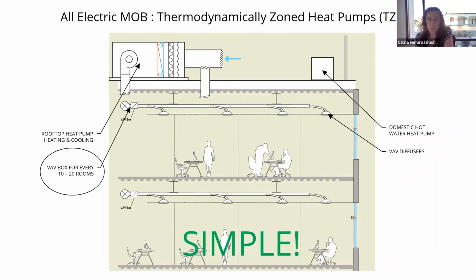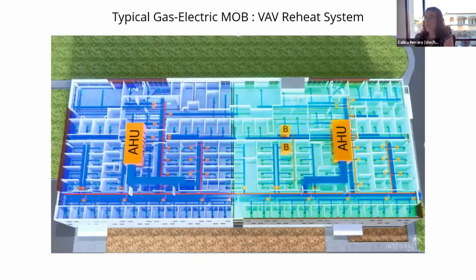You'll also notice there's a lot less mechanical stuff on the page. It ends up reducing the amount of equipment, materials, and also labor for installation, by being able to do all of that at the roof instead of needing to run those additional systems. To give you more of a picture of what this looks like, this is what that conventional system would look like. You can see central air handling units, large ductwork from central distribution taking up that ceiling space, running those large duct mains to get to that full zone, and then this separate hydronic boiler system. And you can see the heating hot water piping routed from that to each of these zones to reheat them as they need it.